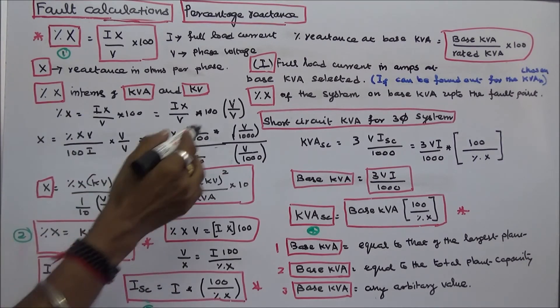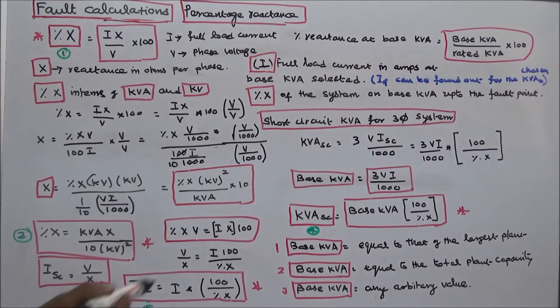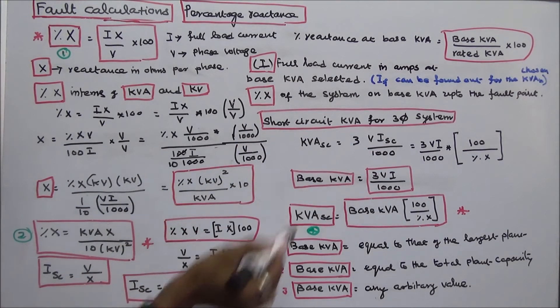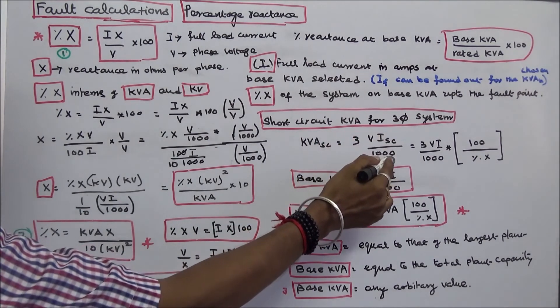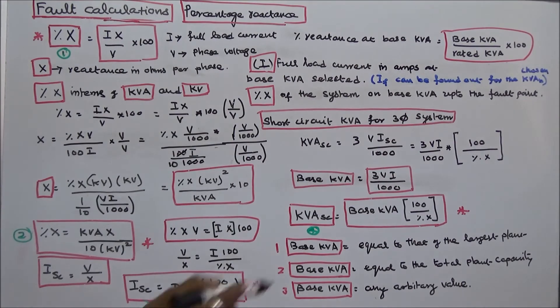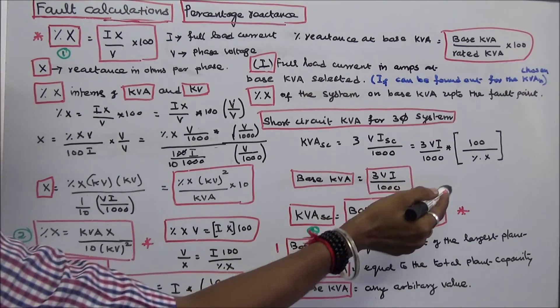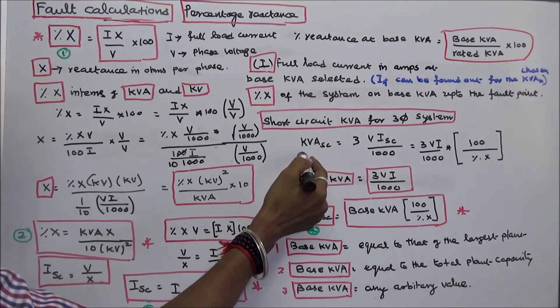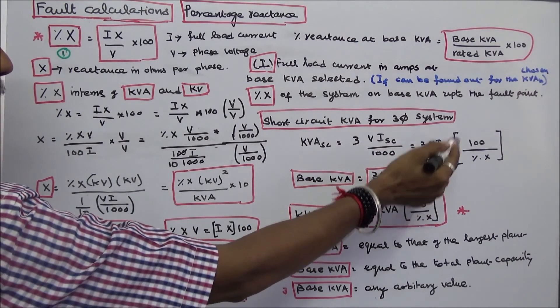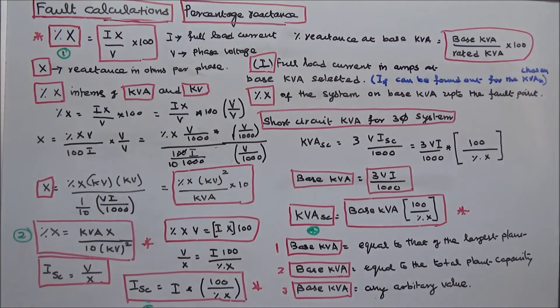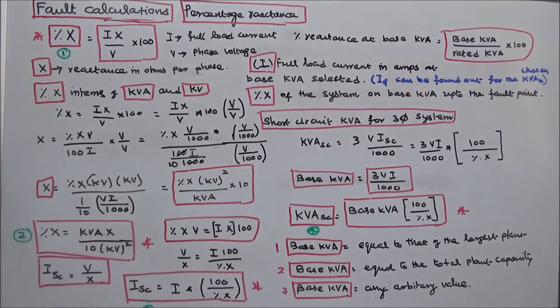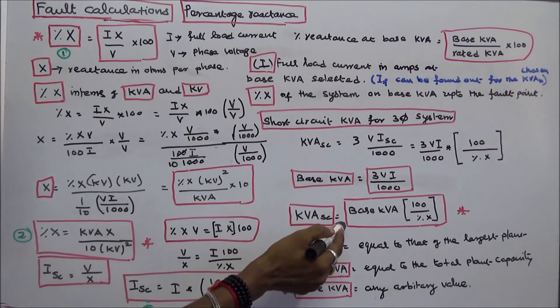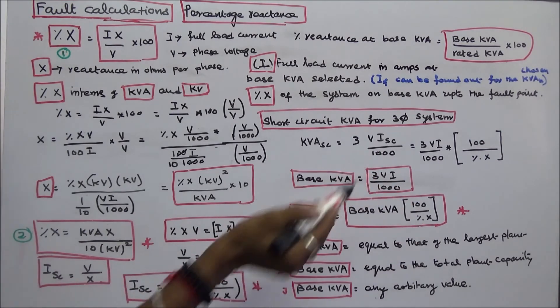For a three-phase system, short circuit KVA equals 3 times V times ISC divided by 1000. Substituting ISC equals I times 100 divided by percentage X, short circuit KVA equals 3 times V times I divided by 1000, times 100 divided by percentage X. Since 3 times V times I divided by 1000 equals base KVA, therefore short circuit KVA equals base KVA times 100 divided by percentage X.